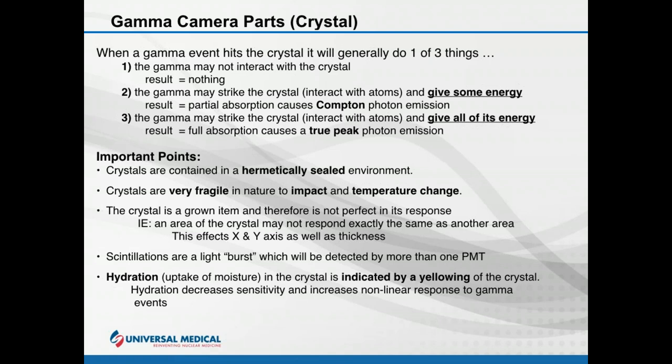When a scintillation or light burst occurs, it will be detected by more than one photomultiplier tube — in theory every tube sees every event, though in reality some outputs will be down in the noise level. Regarding hydration: if a hermetically sealed crystal gets moisture, it causes yellowing of the crystal, which decreases crystal sensitivity and increases nonlinear responses to gamma events. The light isn't as bright because it has to fight through the yellowing, so it responds incorrectly.